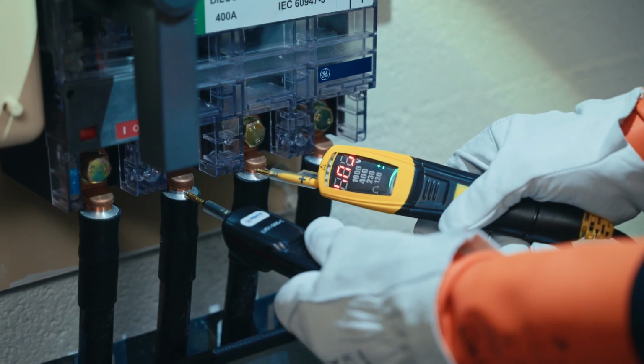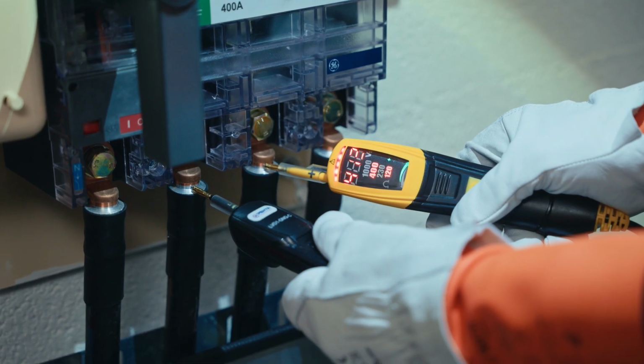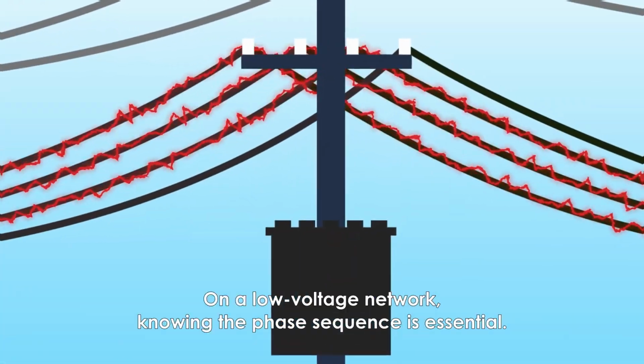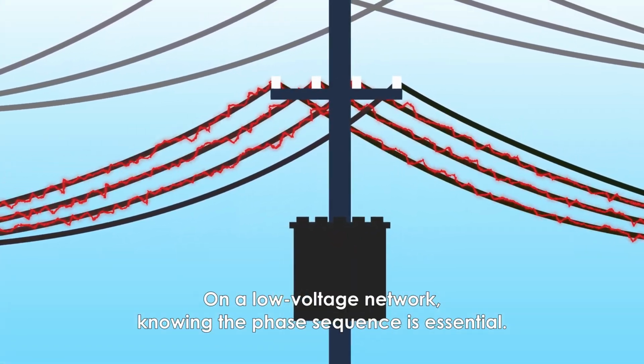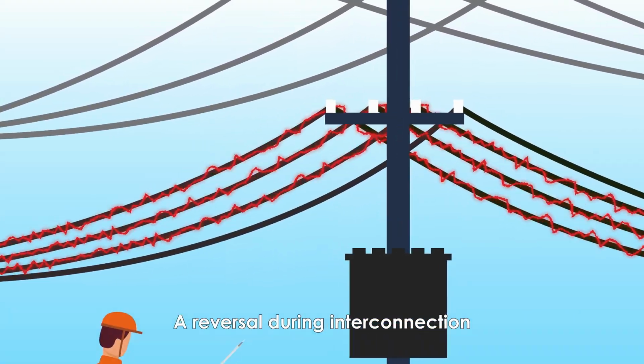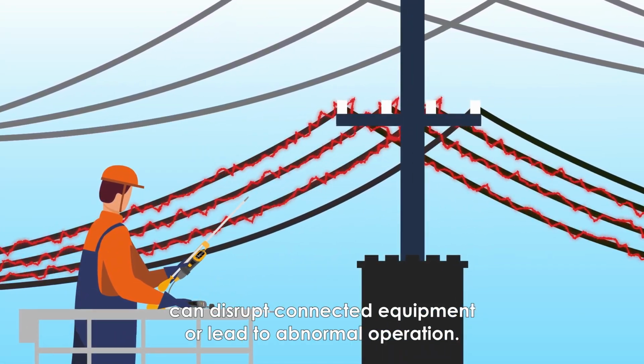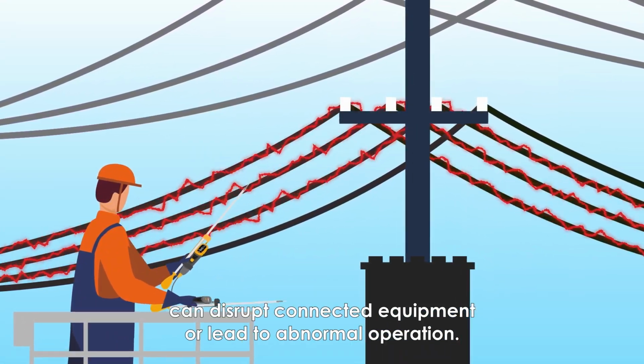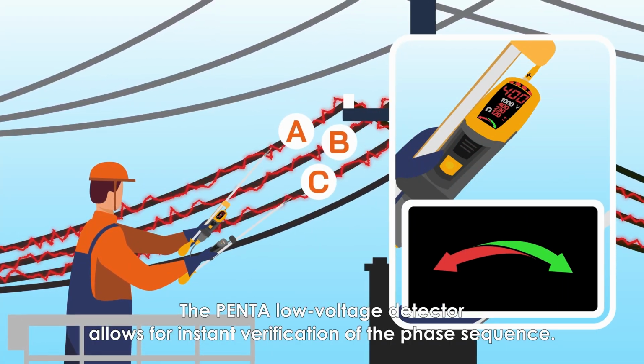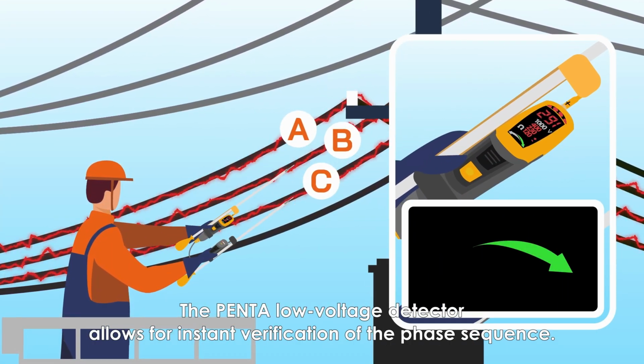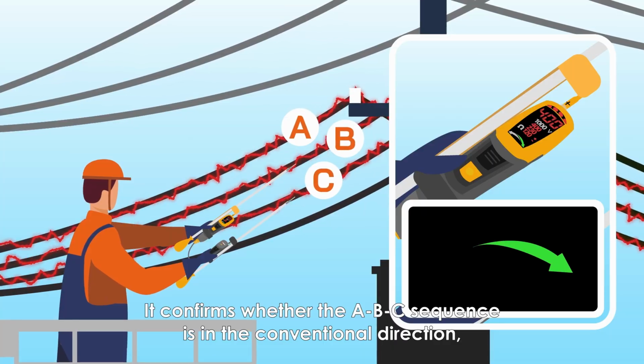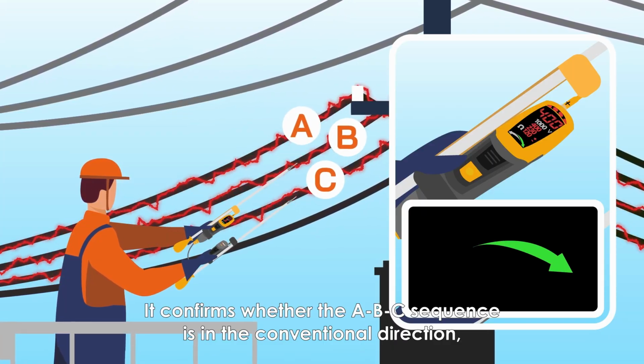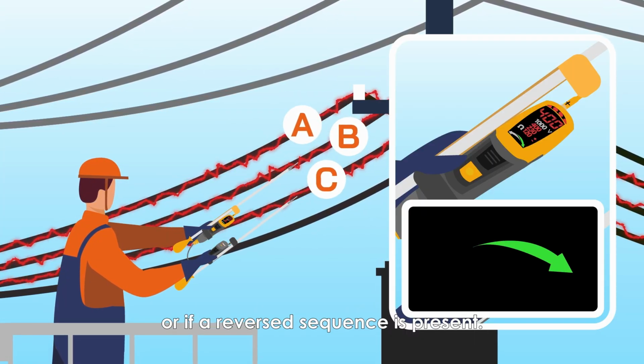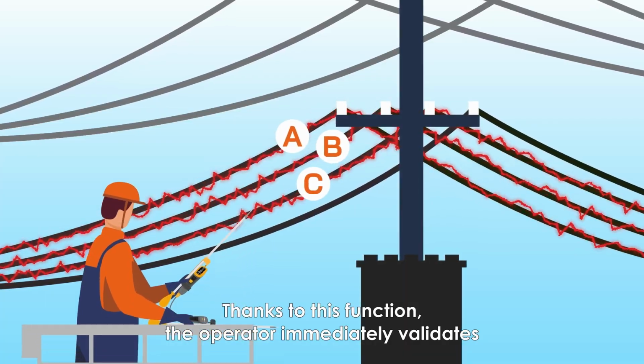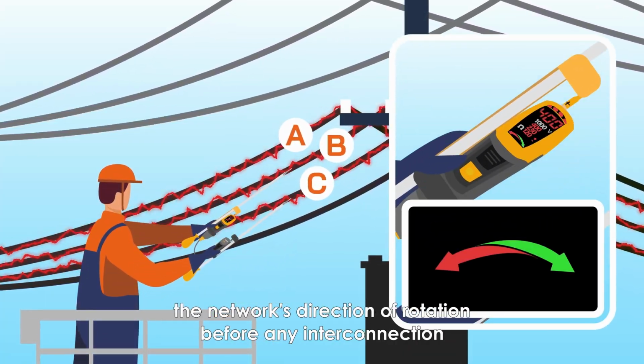Anti-clockwise, clockwise. On a low voltage network, knowing the phase sequence is essential. A reversal during interconnection can disrupt connected equipment or lead to abnormal operation. The Penta low voltage detector allows for instant verification of the phase sequence. It confirms whether the ABC sequence is in the conventional direction or if a reversed sequence is present. Thanks to this function, the operator immediately validates the network's direction of rotation before any interconnection.